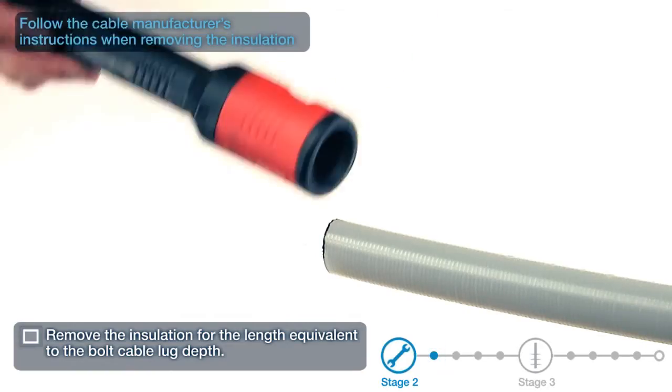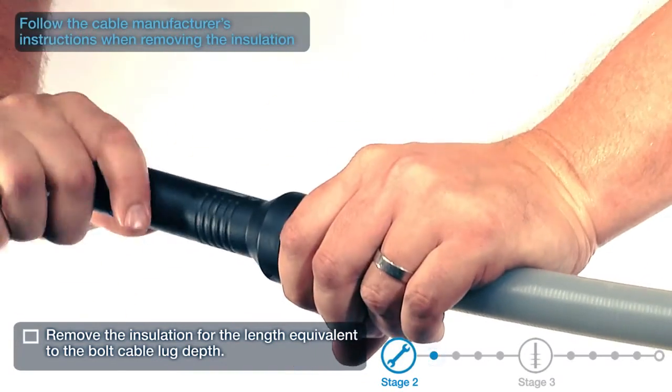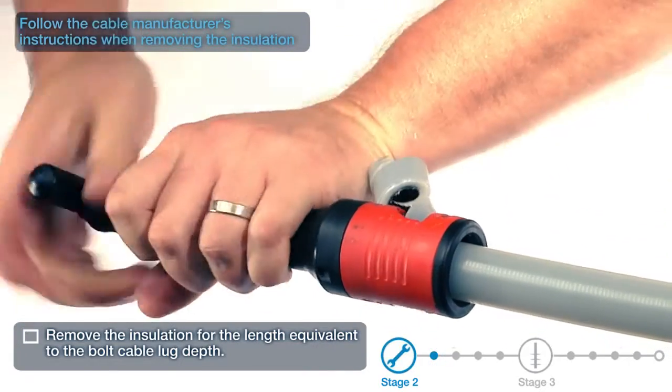Remove the insulation for the length equivalent to the bolt cable lug depth. Follow the cable manufacturer's instructions when removing the insulation.